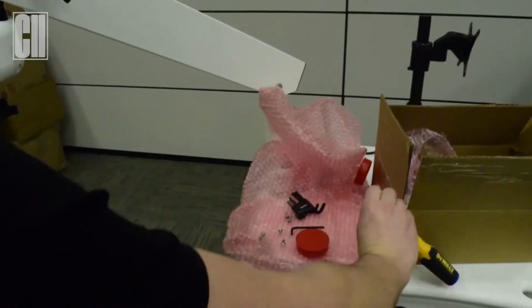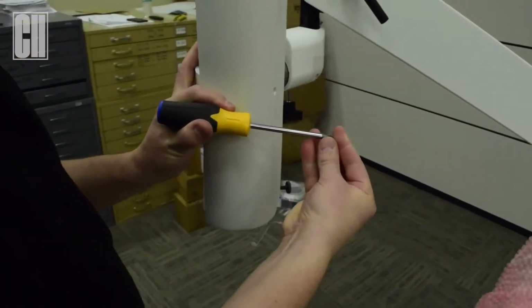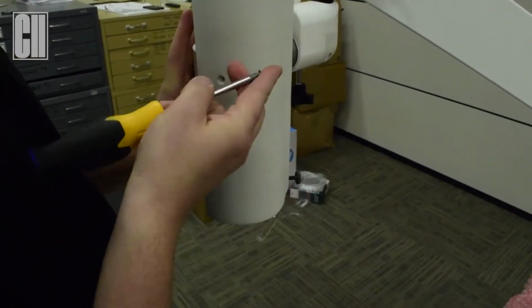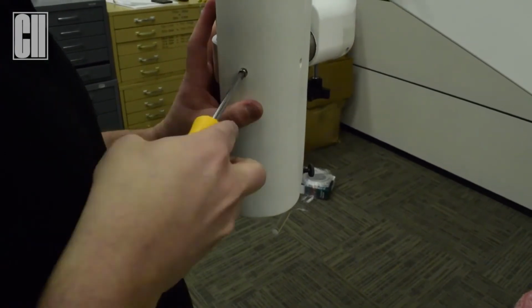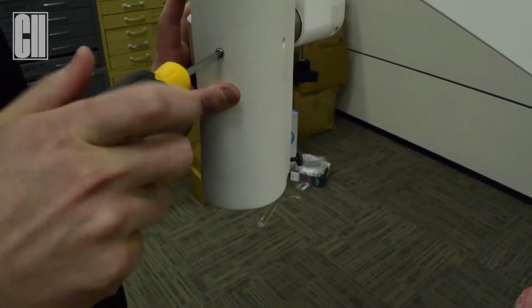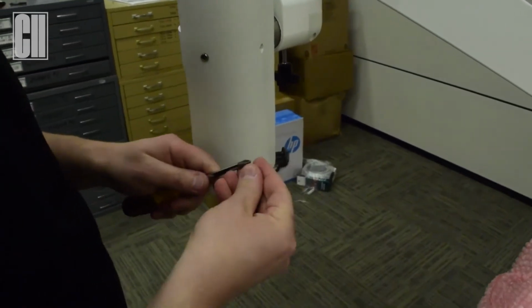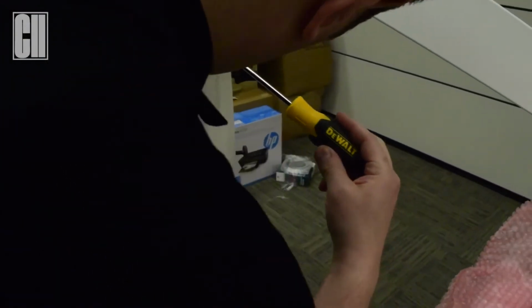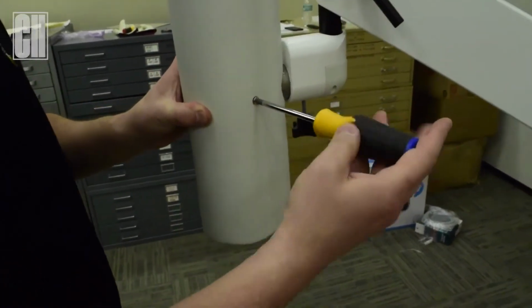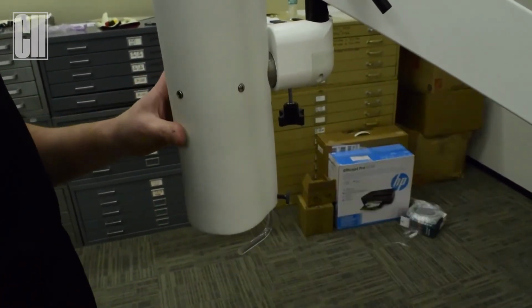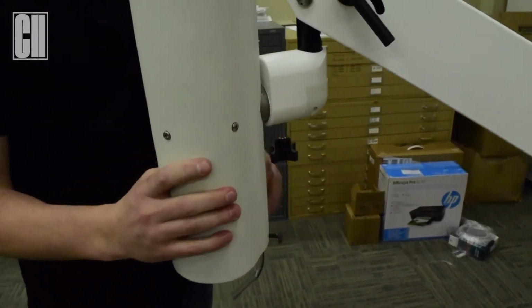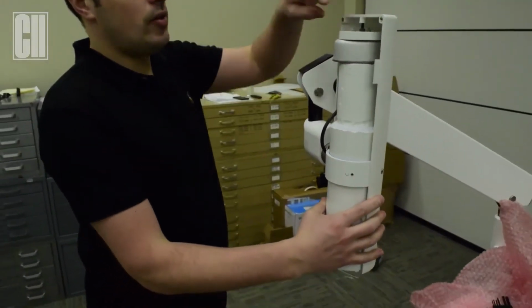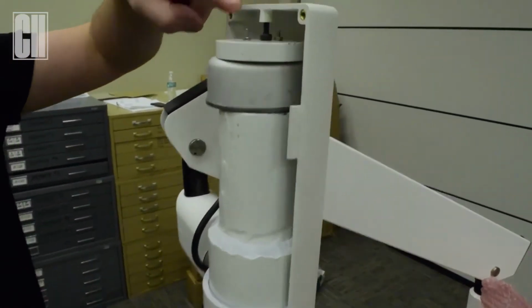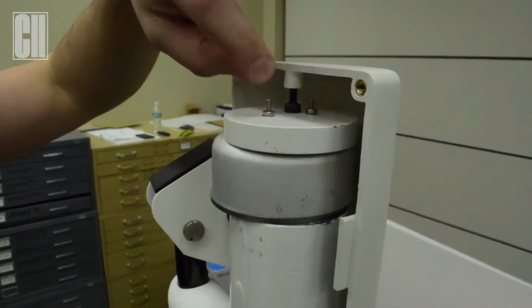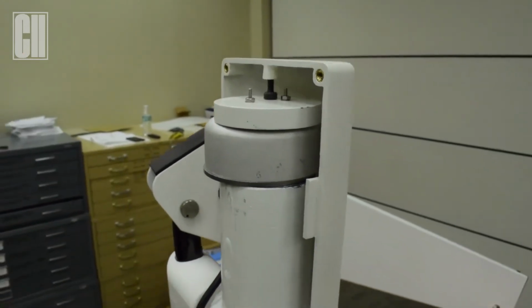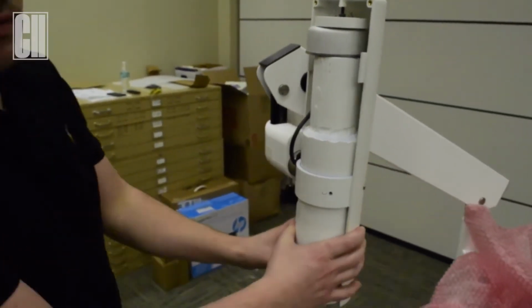Now we don't want to put them in all the way, just a little bit until we have everything lined up. So you just want to get them started on both sides. Once you have those screws lined up, like I said, you don't want to put them all the way in. You have them partially entered, and then you have a stopper screw. You want to make sure that this is pressing up against the probe base so it doesn't allow any kind of movement of the detector. Once we confirm that, we are ready to put on the other side of the casing.